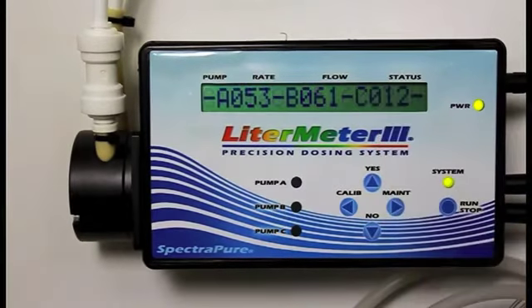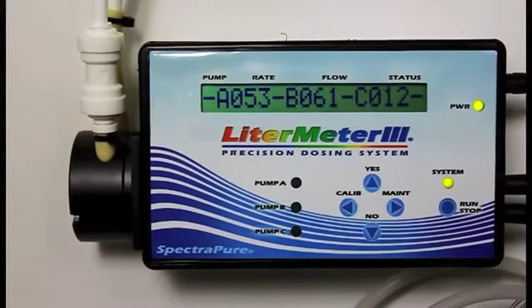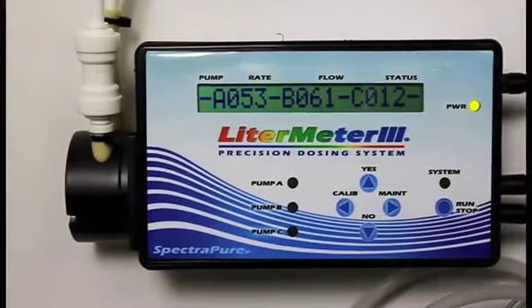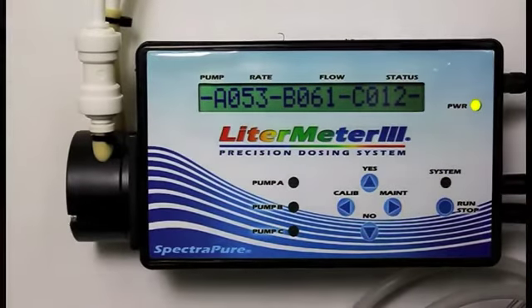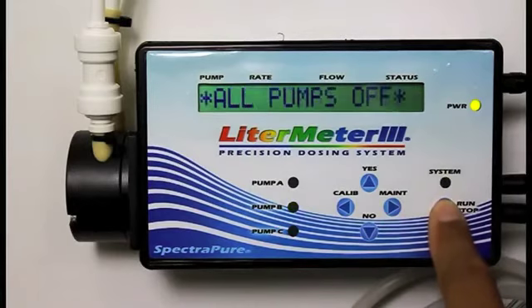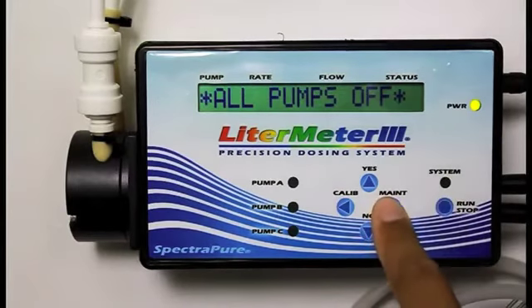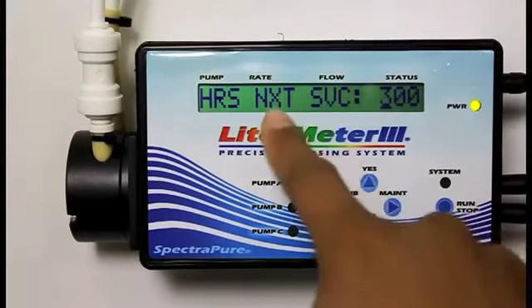This screen displays the operational hours for each of the pumps connected. Pump A has 53 hours runtime, Pump B has 61, and Pump C has 12. This is reset when the timer is reset. To access the service interval timer, press the Run Stop button, then press the Maintenance button, and we can see that the service interval is 300 hours.